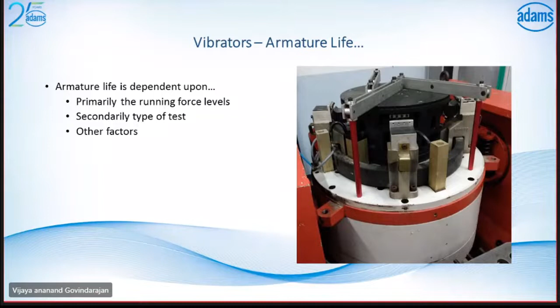So what are the things we need to take care of to increase the armature life? These are the high risk factors that will affect the vibrator armature life. The first is the high temperature of the raw cooling air. Normally the blower connected with the vibrator will suck in air and allow the system to cool. Suppose the blower is not working properly or is not maintained properly, this will affect the armature life. Normally, we provide a flow sensor and a temperature sensor along with the vibrator to maintain the system in a proper cooling manner.